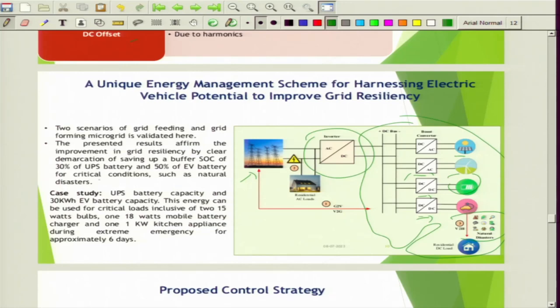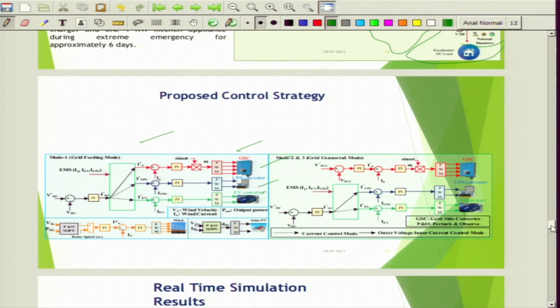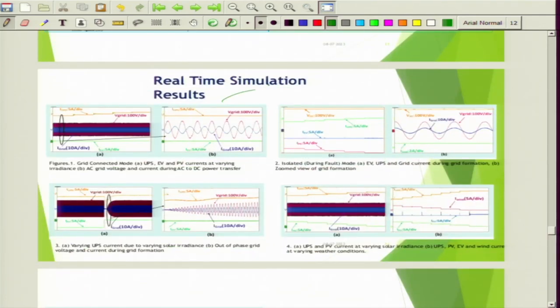We have considered G2V and V2G operations during normal operation scenarios. The proposed control strategies define roles for either the grid side converter, UPS converter, or EV converter depending upon operating scenarios, so they maintain the DC bus voltage. The EV is given the last option to maintain the DC bus so we can preserve bare minimum SOC storage. We have implemented this in Opal RT — with varying irradiation, the DC bus voltage is maintained constant while the UPS, EV battery, or grid side converter maintains the DC bus to improve system resilience.